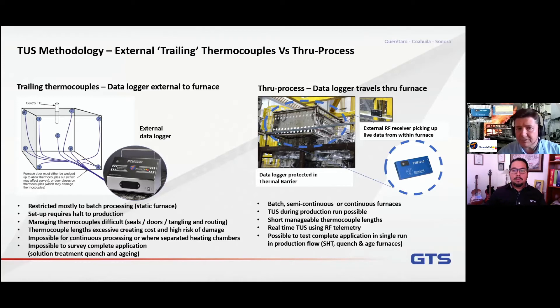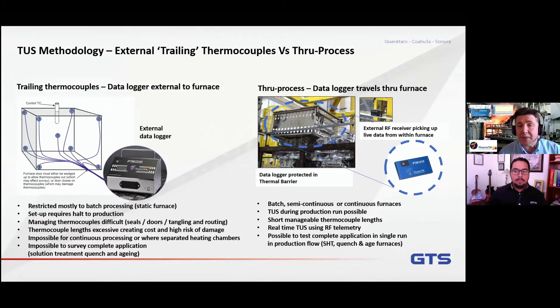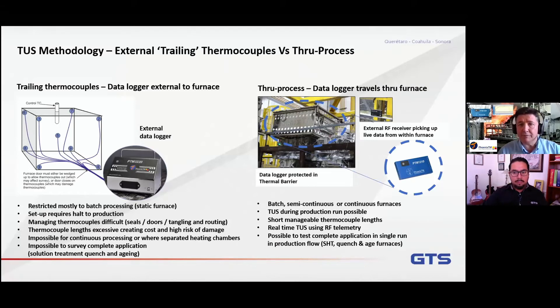There's a little receiver unit shown here. The data logger can be fitted with an RF telemetry system whereby the data being measured is transmitted by radio waves to receivers outside the furnace, giving you live data on your computer. So you can do your survey in real time, the same way as with a trailing thermocouple, but with the safety and ease of use of the system traveling through. And where we're going from the solutionizing furnace to the quench and then the ageing furnace, there's no way you could do that with a trailing thermocouple — the only way is by having something able to transfer from one process to the next in sequence.